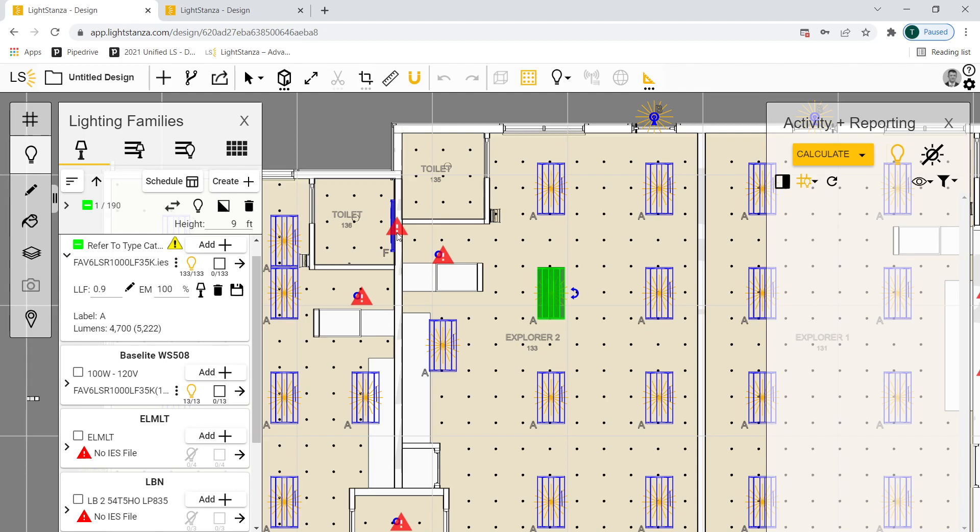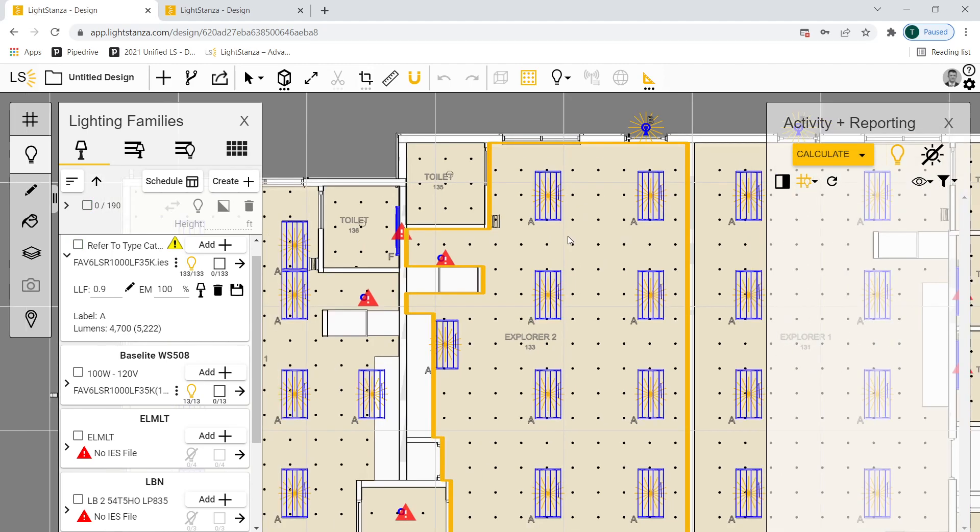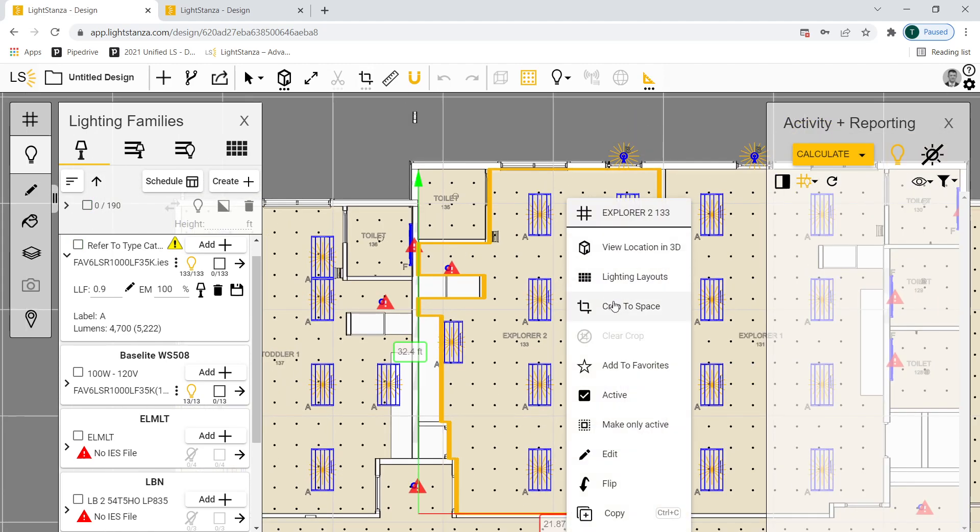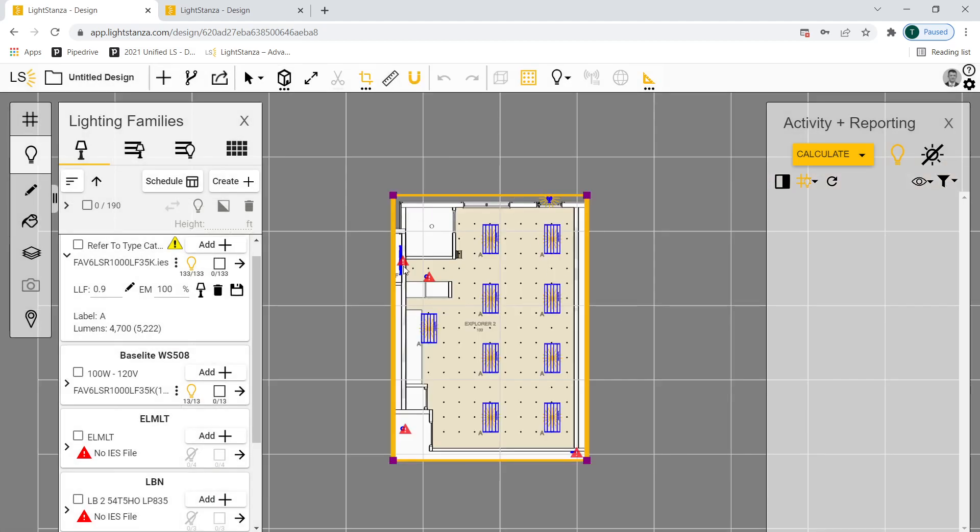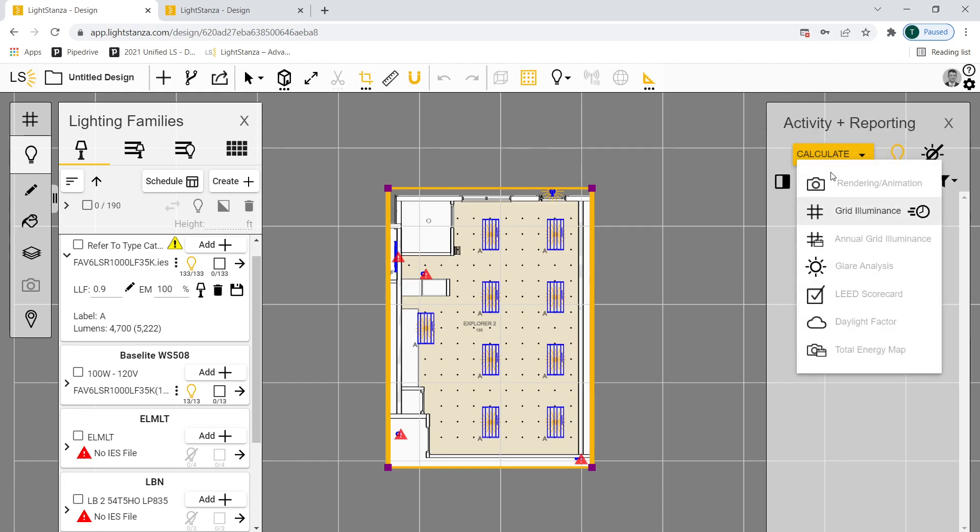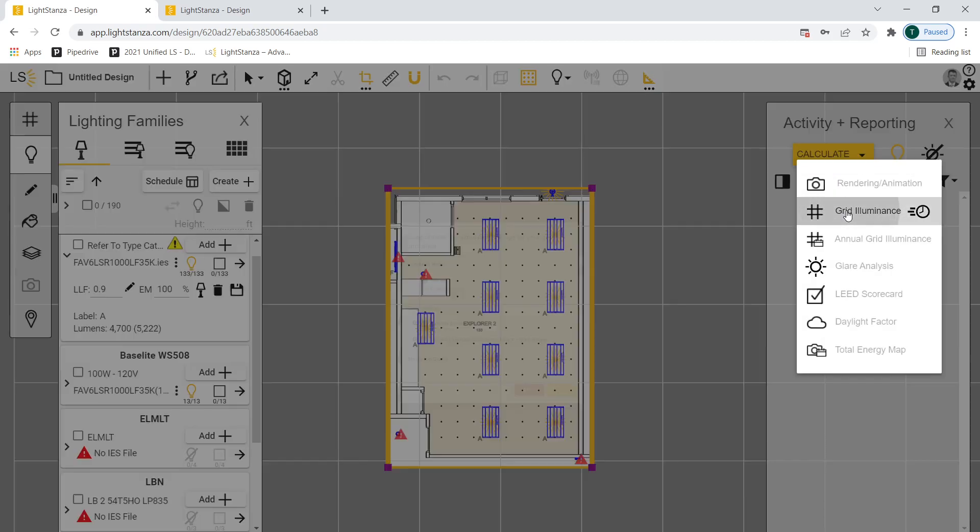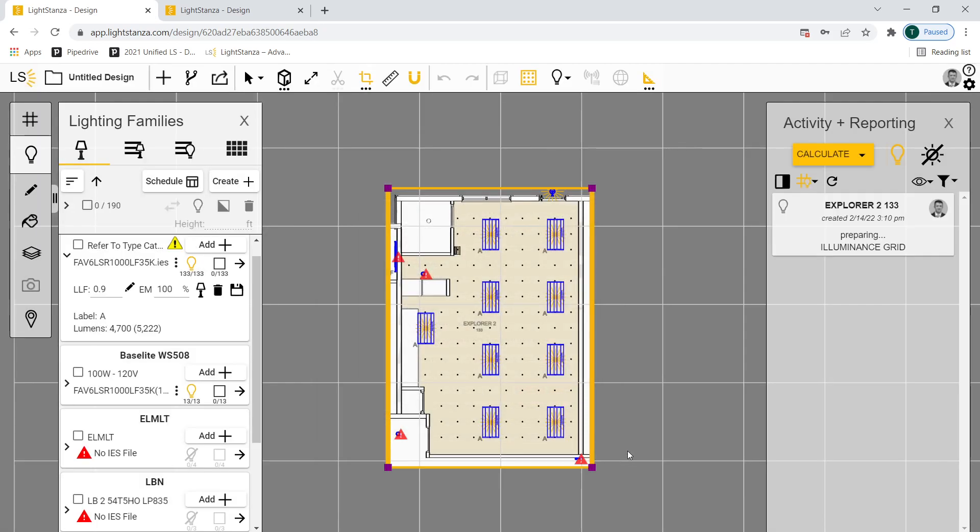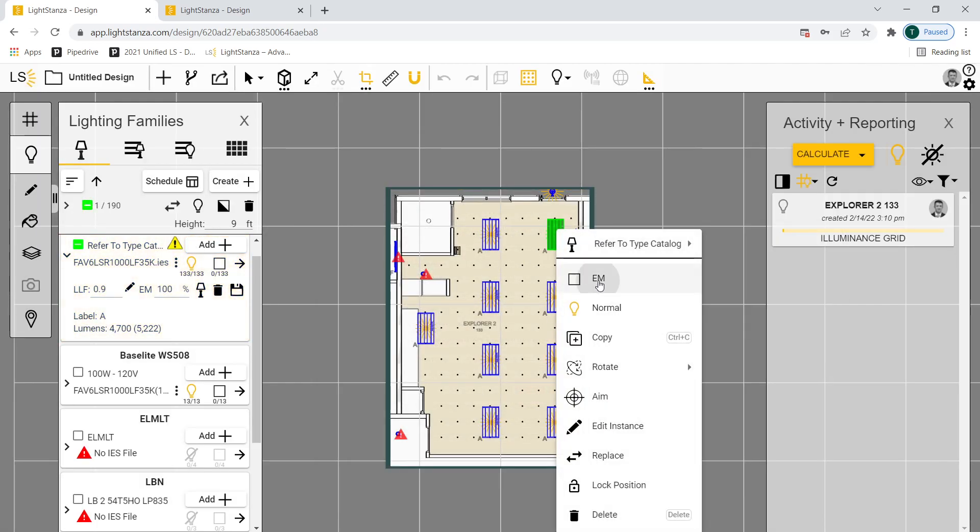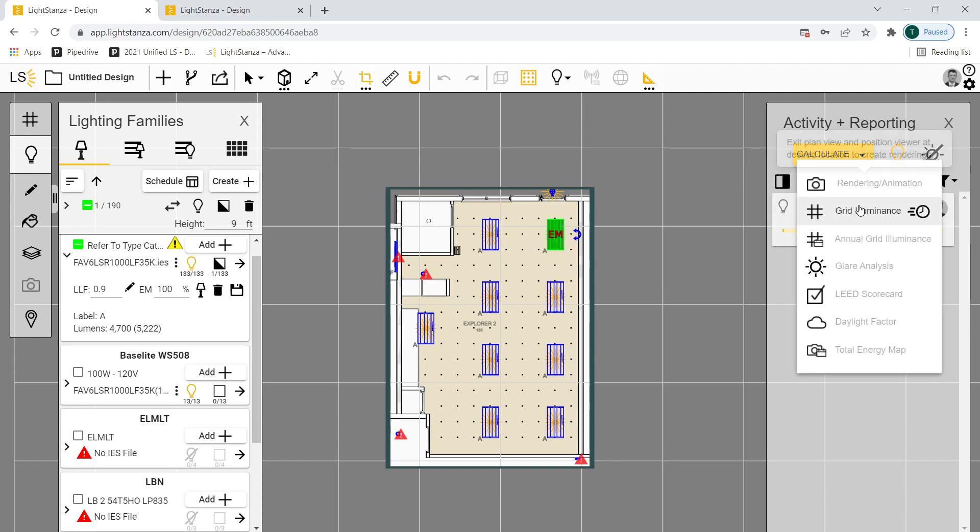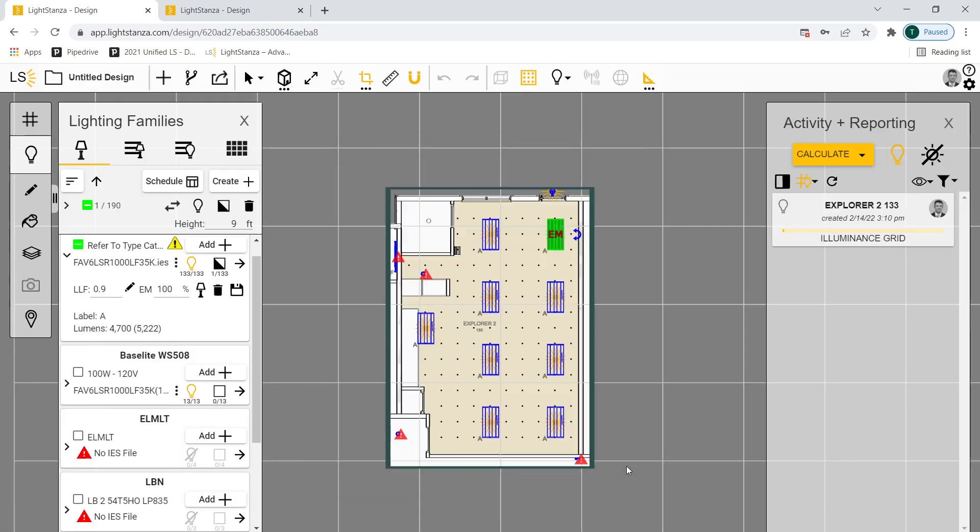So hopefully with this demonstration, you've seen the benefits in this. And if I wanted to start running calculations, I can right click, crop to this space. That's going to temporarily hide all those other light fixtures and all of that other building geometry. So I can start running calculations just on this room. So if I come up to calculate, I'll run a normal power calc. I'll even add an emergency fixture next to this door, make it emergency. I'll come up here, run another grid illuminance for emergency.